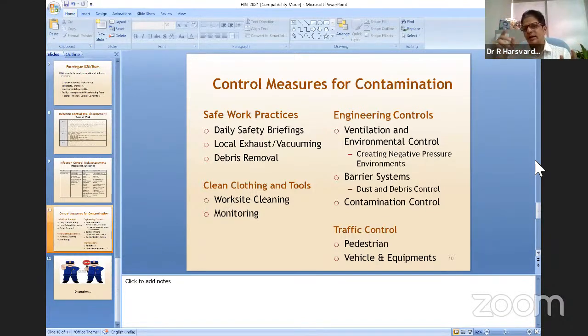The whole idea is that in no way should there be reverse airflow leading to intermingling of the SPMs or microbes from the lesser clean or unclean or lower zones to higher zones. So in an OT suite complex, when we design the layout plan, we design it from the concept of zoning, and this concept of zoning is inherently built in with the concept of graded pressure from higher to lower. So that's another way of avoiding it.